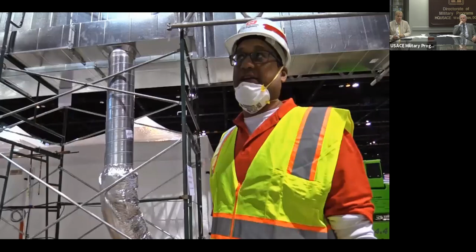The main aspect of these rooms is that we can create negative pressure. These were specially ordered from a firm in Eugene, Oregon. The main components in here include a HEPA filtration system that circulates the air out at least 12 times per hour. It pushes the air to the central HVAC system and exhausts it through fans, filtering it before it goes outside the building.